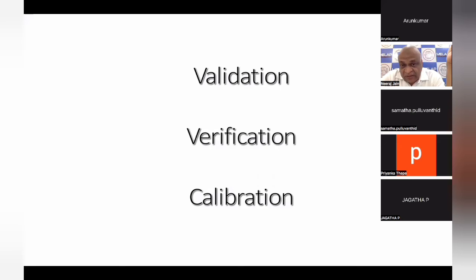Similarly, for that higher reference material also, we calculate values based on further higher reference material. That way, they say we reach the national international standard. This process by which our results are traceable through the calibrator to the national international standard through an unbroken chain of comparison is called metrological traceability. Metrology means study of measurement. So this is the concept of validation, verification, and calibration, which is important. Everybody shall have clear knowledge of these concepts.